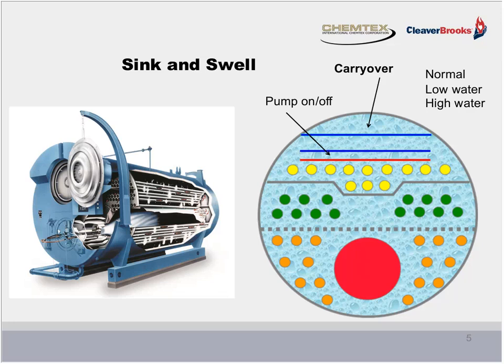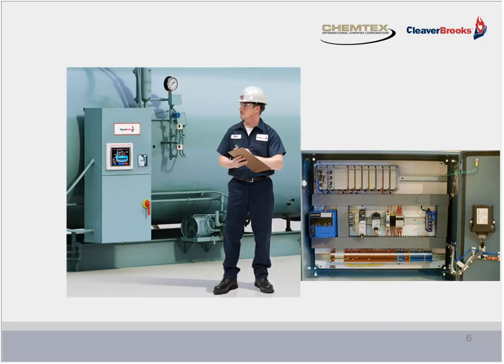And oftentimes when this happens, the feed pump cannot keep up, and the boiler experiences a low water condition, causing the unit to shut down. The total phenomenon of the rapid rise and fall of the boiler feed water is therefore referred to as shrink and swell.